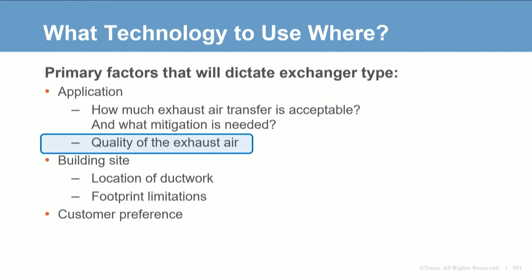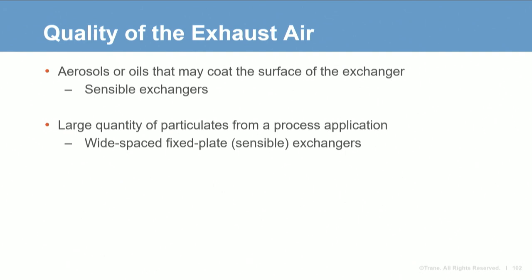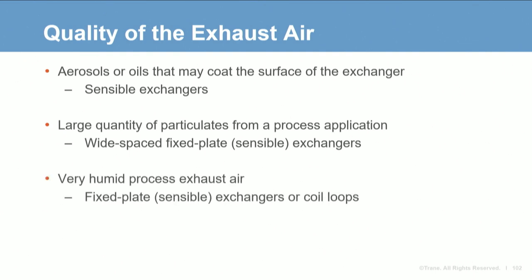In some cases the type of exchanger is driven by how much exhaust air transfer is acceptable; in other cases it's driven by the quality of the exhaust air. For instance, if there are oils or aerosols in the exhaust airstream that can coat surfaces and prevent latent transfer, sensible exchangers should be used. If there's a large source of particulates or soot that could accumulate on exchanger surfaces, wide-spaced metal plate exchangers are the best fit since they're easiest to clean and have the widest spacing. If the exhaust air is very humid, sensible plate exchangers or coil loops are the best fit, as they are designed to handle and remove large amounts of condensate.